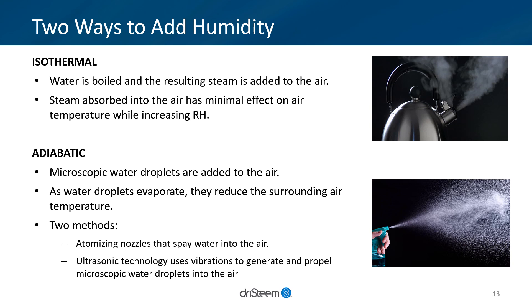The second way to humidify is adiabatic humidification, which adds microscopic water droplets into the air. As water droplets evaporate into the air, they reduce the surrounding air temperatures, providing free cooling while humidifying. Adiabatic humidification can be achieved with two different methods: atomizing nozzles that spray water directly into the air, or ultrasonic technology, which uses vibration to generate and propel microscopic water droplets into the air.